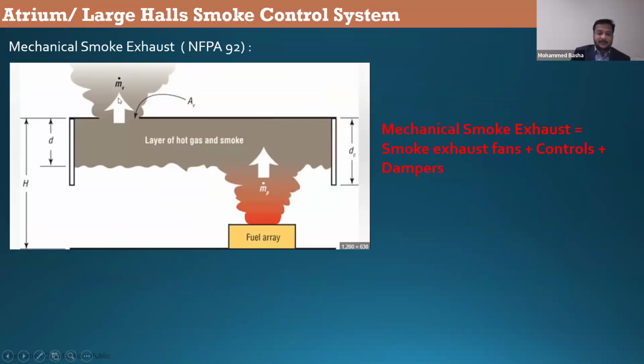You will have smoke exhaust fans in the top or in the side, which will constantly take the smoke out of the protected area to maintain the smoke interface layer. We call this the free area, and this is called the smoke interface layer. The smoke interface layer means the layer that separates the hot gas and the cold gas. The layer below the smoke interface layer is called the tenable environment. So mechanical smoke exhaust is smoke exhaust fans, controls, dampers, of course the fire alarm system, damper operations, and of course fresh air fans.